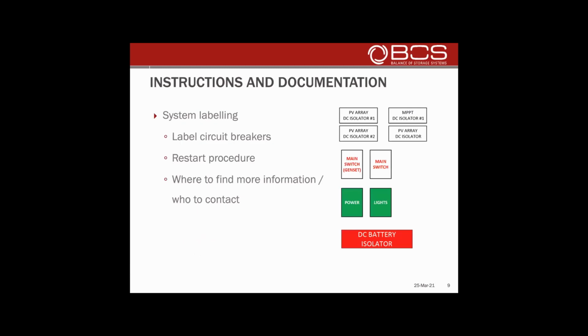Instructions and documentation come down to your installation and the equipment you purchase. One key thing when helping a customer over phone or email is clear labeling of what parts of the system do or are having an issue, particularly circuit breakers like isolators for the battery bank, PV arrays, generator, and output power and lights. This really helps when determining an issue, because if a customer says a circuit breaker keeps turning off, but it's not labeled, it's really difficult to know what that circuit breaker is doing.